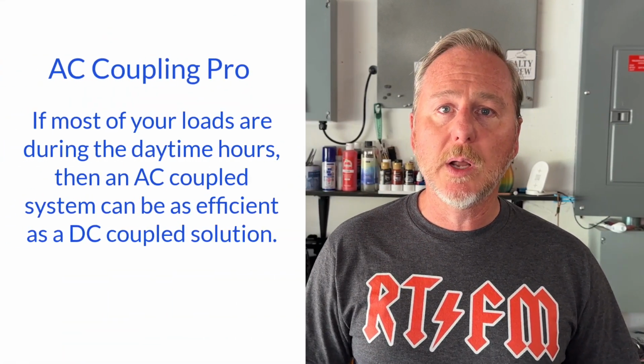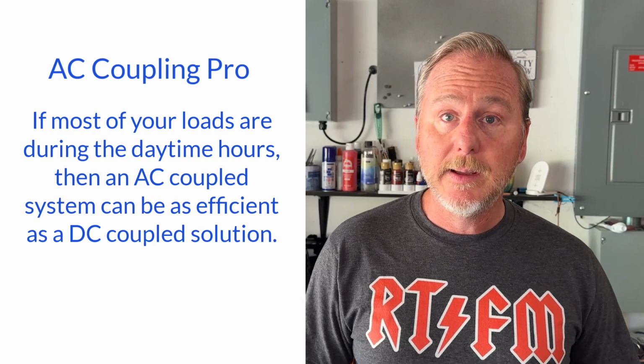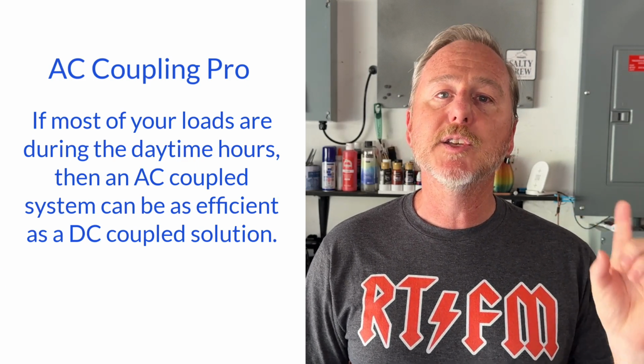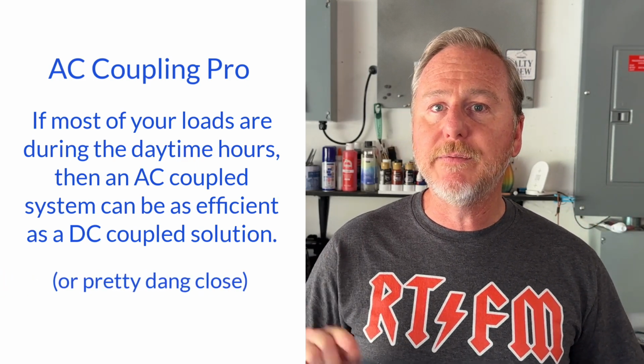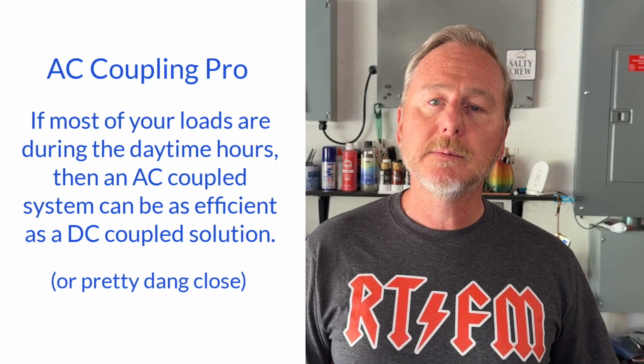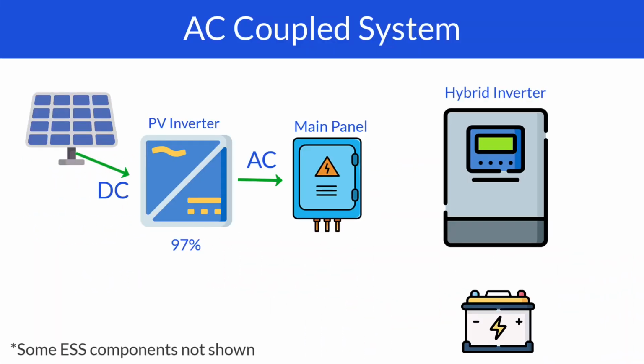If most of your loads are during the day, then an AC coupled system is more efficient, or as efficient as a DC coupled system. Okay, so if most of your loads are during the day, that means as soon as the inverter converts the DC to AC, those AC electrons are directly consumed by the loads.